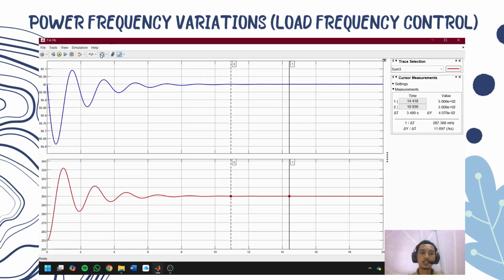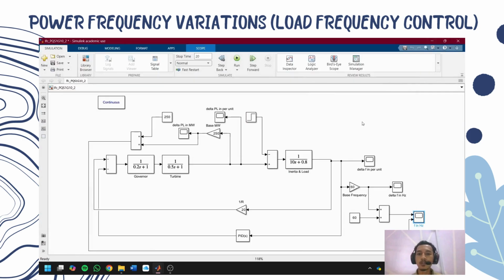So this is after we insert the PID controller to mitigate these power quality issues, which is about power frequency variation. The frequency has been balanced by the PID controller to 60 Hz, and the power has been stabilized to 300 megawatt from 250 to 300 megawatt. This is because the PID controller has calculated the error value, and the output has become the desired value. So that's all for this simulation. Thank you.